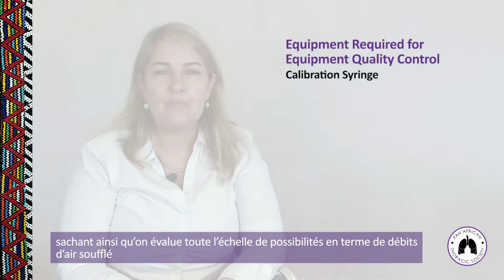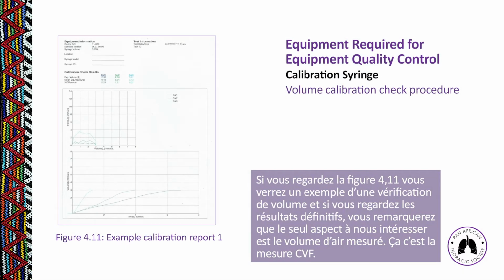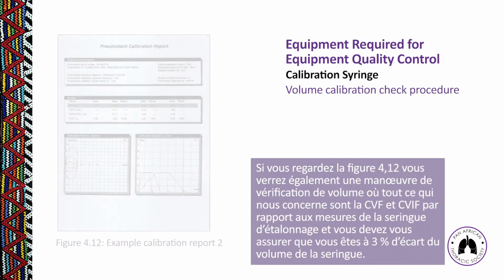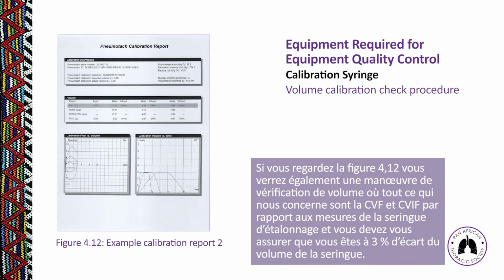If you look at figure 4.11, you will see an example of a volume calibration procedure. And if you look at the actual final measurements, you will see that we are only interested in looking at the volume of air measured. That is your FVC measurement. If you look at figure 4.12, you will also see a volume calibration check procedure where all we would look at is the FVCs and the FIVCs and check those against the syringe volume to make sure that the volume of air being read is within 3% of the syringe volume.